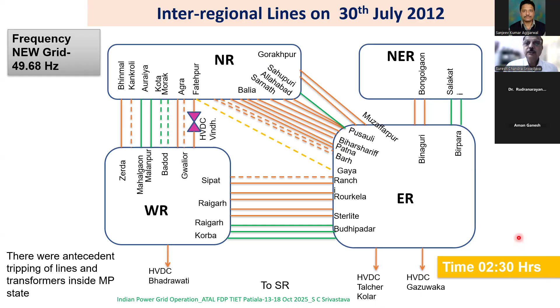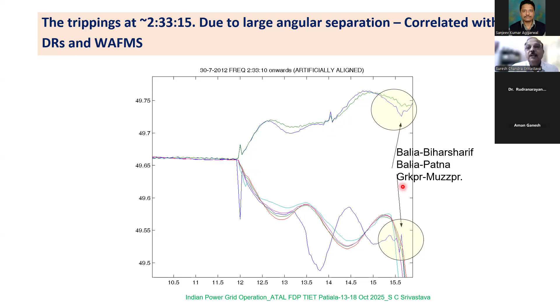We had very few PMUs, as I'm mentioning. In the northern region, this is the frequency going down after the outage of the Bina line, and then here the total collapse of the grid is taking place. So 2 or 3 PMUs in Western and 4 or 5 in Northern region really helped the committee to find out what had really happened. We got the substation data, took the timings, and tried to understand why each jump is there. Each jump indicates some kind of event. It is there in the report. That is why I'm emphasizing that this is a very good technology for situational awareness. If it had been in large numbers, then probably the situation would have been different.